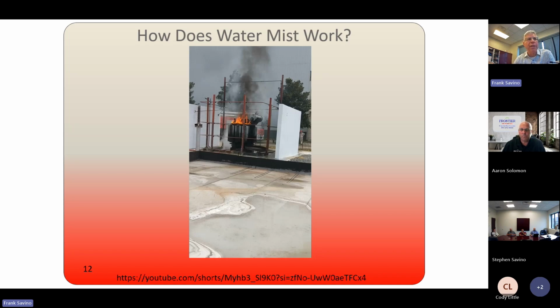So that is a really good depiction. Did that actually put out the oil fire on the transformer, or did it just knock it down to be controlled? Okay. The requirement for Factory Mutual to get listings for water mist, unlike sprinklers, is that you must extinguish the fire. If you don't extinguish the fire, you do not pass, you do not get a listing. All of the water mist nozzles per Factory Mutual must extinguish the fire. There's no such thing as control or suppression to obtain a listing.